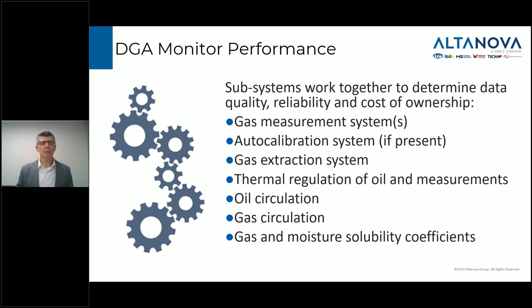So yeah, I'd like to start with the basics. We'll start simple with the 1 and 2 gas monitors. These typically measure hydrogen in the oil because the great majority of transformer faults will generate hydrogen. Some of them can also measure and report carbon monoxide, which can be associated with faults affecting the cellulose insulation. The purpose of these types of monitors is really fault detection. They can't help diagnose exactly what kind of fault is going on. So their role is really to detect as early as possible a changing condition that's generating gases.